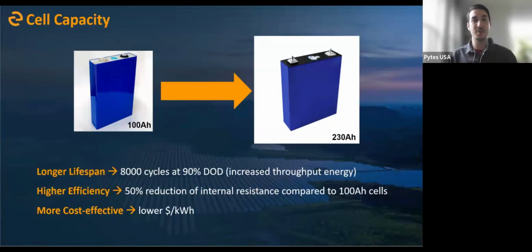Across the board, all of our low voltage products, the E-Box, V5, the Pytes stackable battery, and our high voltage products currently employ 100 amp hour prismatic cells, which has been the industry standard for at least a few years. One of the biggest changes on the V10 to get that higher capacity into the 10 kilowatt hour range is using a larger prismatic cell, now 230 amp hours.